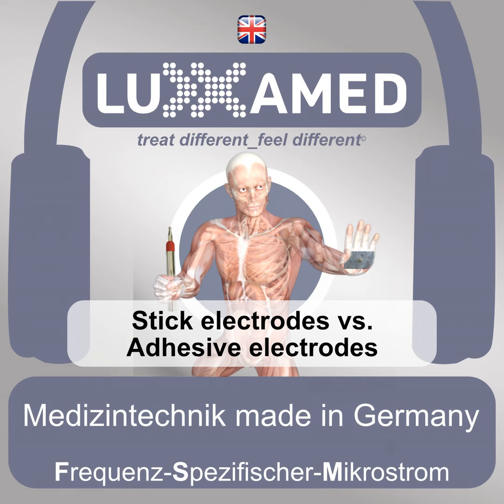Okay, let's go to the advantages and disadvantages of adhesive electrodes. Of course, they are easy to use. They are hygienic when you use them correctly. They can be used on almost all parts of the body, but observe the warnings in the instructions for use. Maybe there are some parts where it is not recommended or not allowed to place the adhesive electrodes. You have a low time expenditure. Movement, stretching, and manual therapy are possible in parallel to the use of the microcurrent therapy. Then you can use them multiple times, but also here, as we saw before in the marking part, follow the instructions for use. And of course, they are available in many variants and sizes.